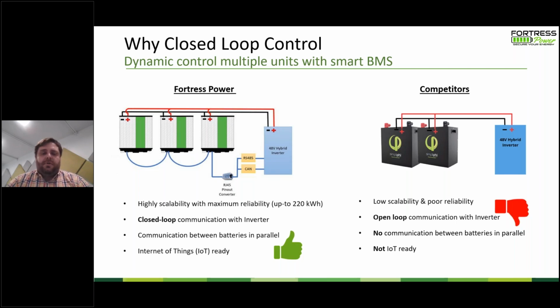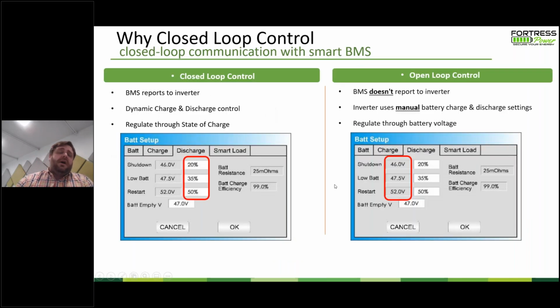So it is encouraged that you select an inverter that's compatible with closed loop control with the battery, although it's not necessary to, particularly with oversized batteries. So when you're doing large off-grid camps, then the battery to inverter communication becomes less important because you have well oversized batteries. But when you have smaller batteries that are only designed to run a couple of hours for the whole house backup system, that's when that closed loop communication becomes more important.